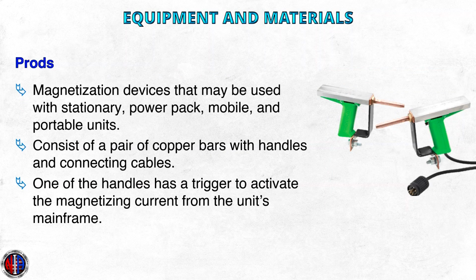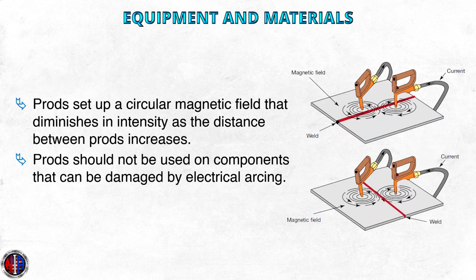Prods. Prods are magnetization accessories that may be used with stationary, power pack, mobile, and portable units. They typically consist of a pair of copper bars 0.5 to 0.75 inches in diameter with handles and connecting cables. One of the prod handles has a trigger to activate the magnetizing current from the unit's mainframe. Prods establish a circular magnetic field that diminishes in intensity as the distance between prods increases. Prods should not be used on components that can be damaged by electrical arcing.